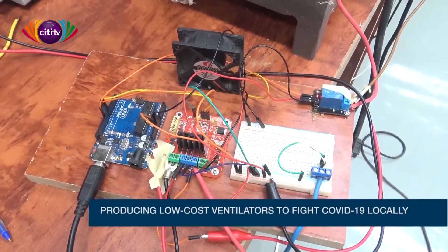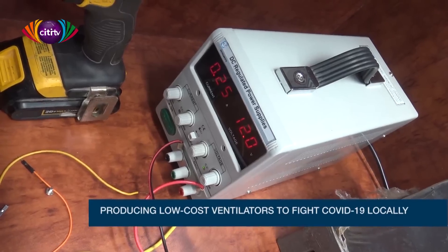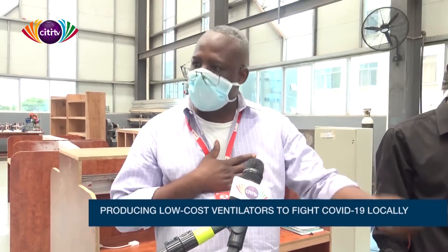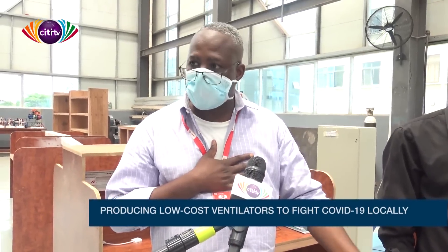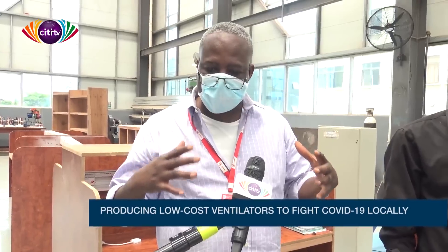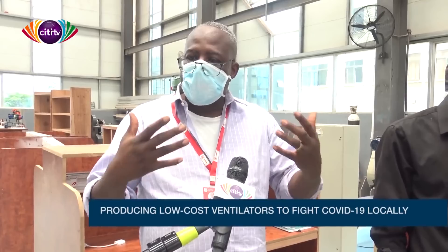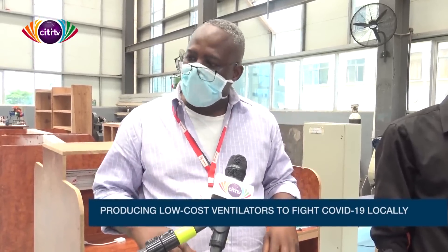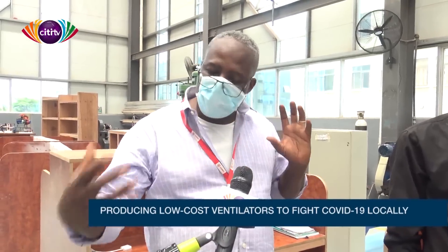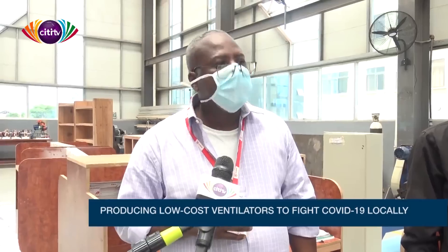In the next development stage, a pressure sensor will be connected to the patient to monitor pressure so that when the patient begins to breathe on their own, air isn't forced in and the patient doesn't drown in air. This is a critical design consideration: when lungs are completely collapsed the mechanical vent helps resuscitate, but once the patient starts breathing the system must synchronize with their breathing cycle — otherwise pushing air in while they push air out could kill the patient.